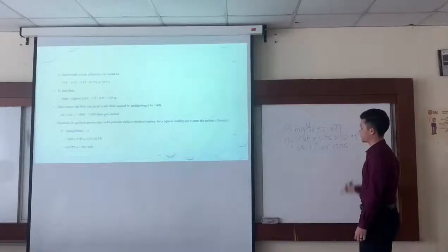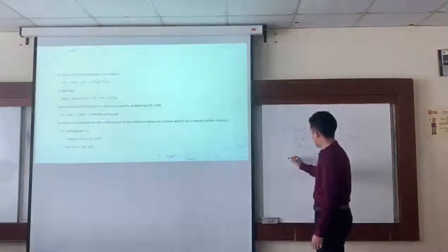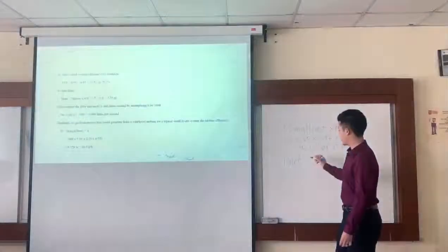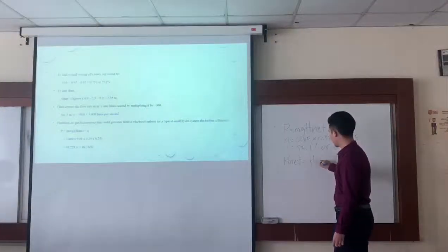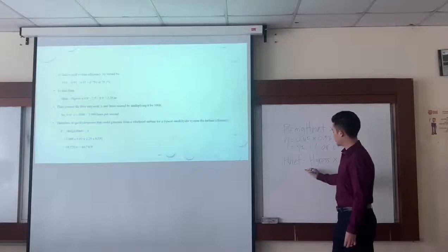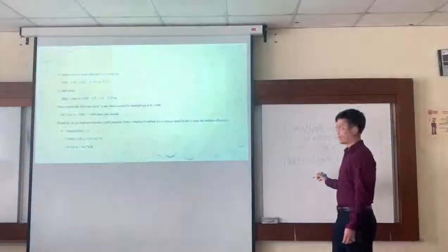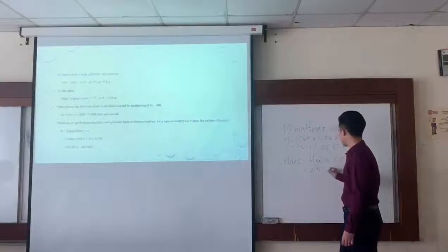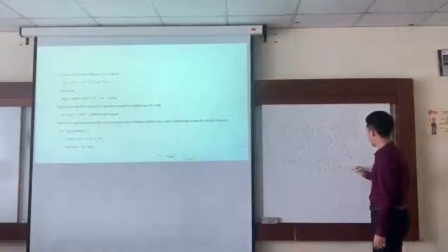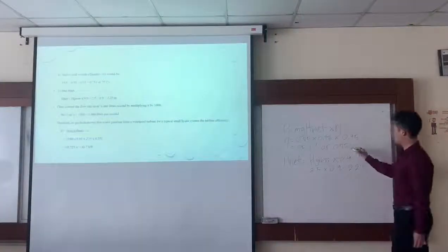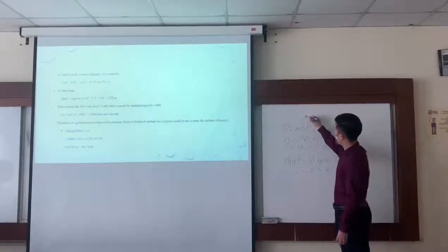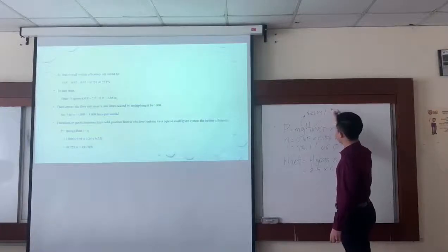So first we get the efficiency, and the next one would be H net. Like I mentioned before, the H net is H gross multiplied by 0.9. From the question, we know that H gross is equal to 2.5, as given. Multiplied by 0.9, you will get around 2.25 meters. So you get the efficiency, you get H net, and G, you know, is 9.81 meter per second square.